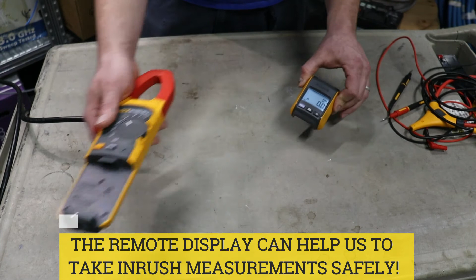You can measure inrush using the jaws as well as the iFlex probe. In most cases, the iFlex probe is the way to go for inrush measurements. You can wrap it around bigger conductors in tighter areas. It's a great little addition.